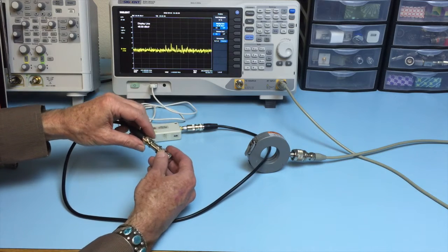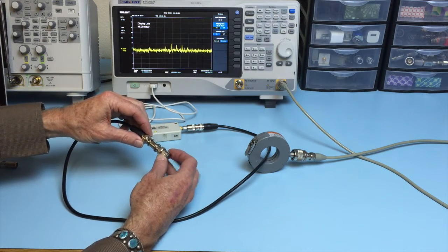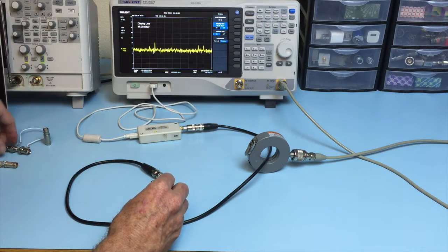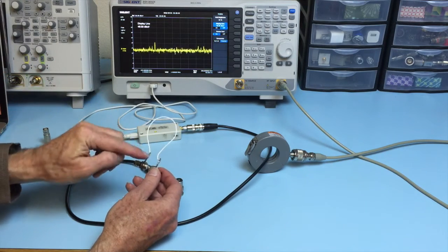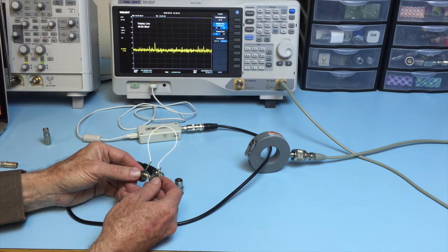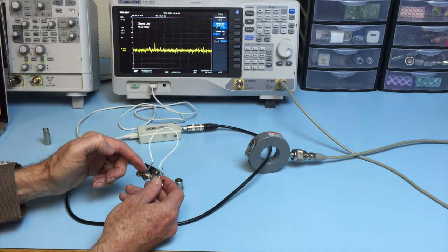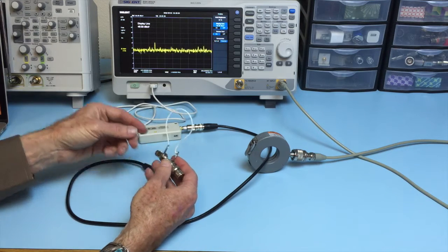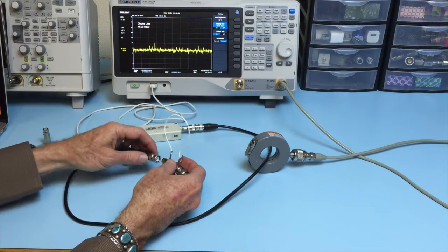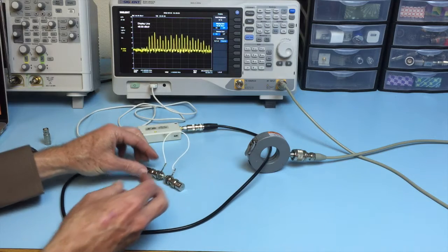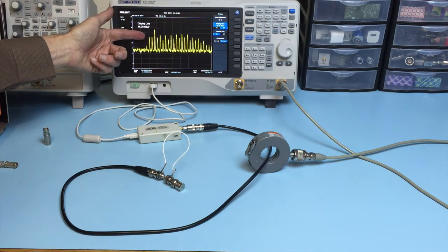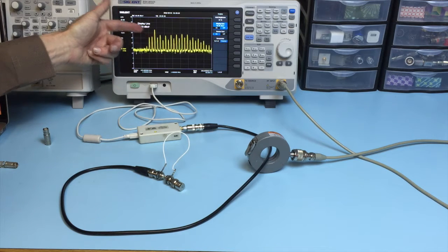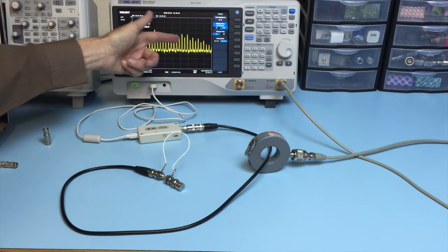So notice that I have a barrel connector connecting the load to the coax. We're going to replace that with this large loop of wire that's going to simulate a long pigtail in the shield circuitry. So I'm going to reinstall the 50 ohm load, and we'll connect this up to the cable and see what happens. Now, as you can observe, the harmonic content has jumped up 20 to 30 dB across a range of about 100 megahertz to 300 megahertz.